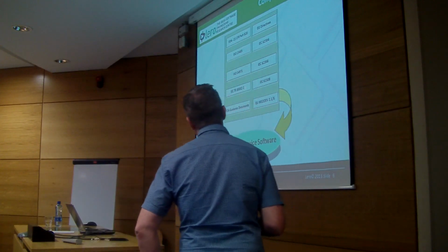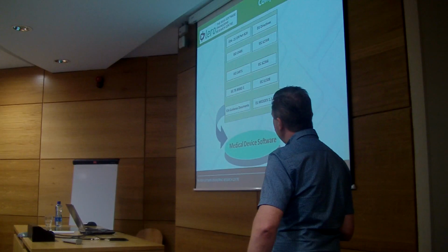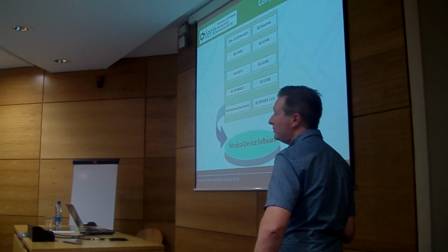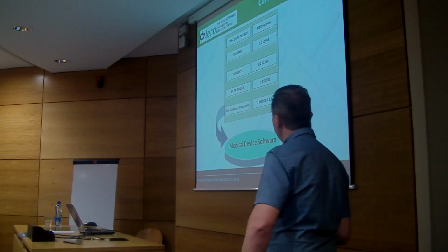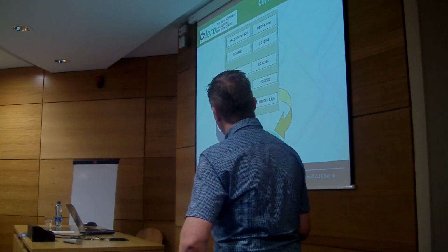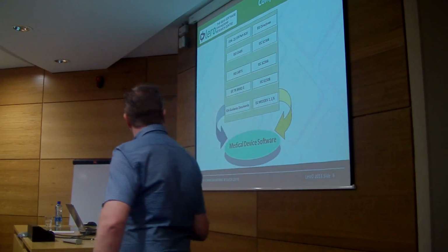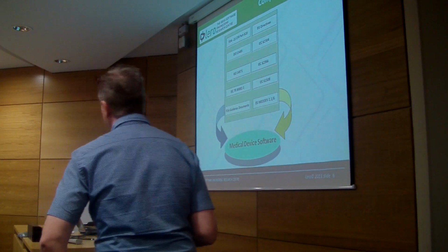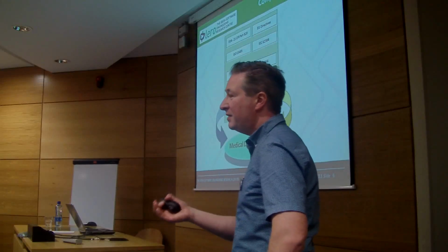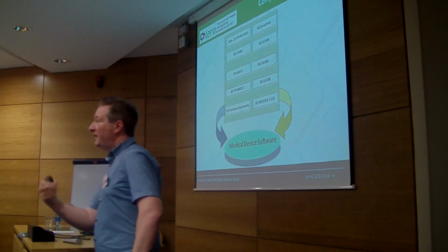Also, it's safety critical software you're developing. So you need to comply and align yourself with the risk management standard for medical devices, 14971. There's also a guidance document which is specific to how you apply 14971 for software, which is 80002-1, which I think should be looked at as well. Usability is becoming more and more important within the medical device domain.